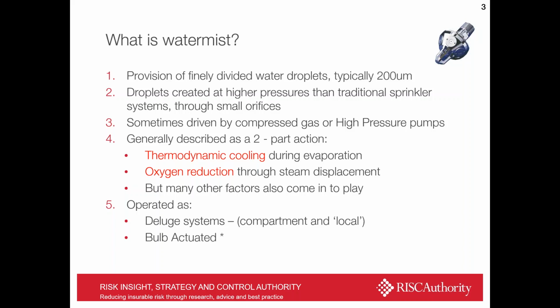These systems can be implemented in a number of forms. Traditionally, they've been what we call deluge systems, where the heads will not have a glass frangible bulb in them, but will actuate on an open pipe system when the pump is switched on. And these can be operated on a compartment or local application protection. But increasingly, we're seeing systems which are bulb actuated. And we've got some rather strong feelings on some implementations of those, which we don't feel might be appropriate. But more on that later.